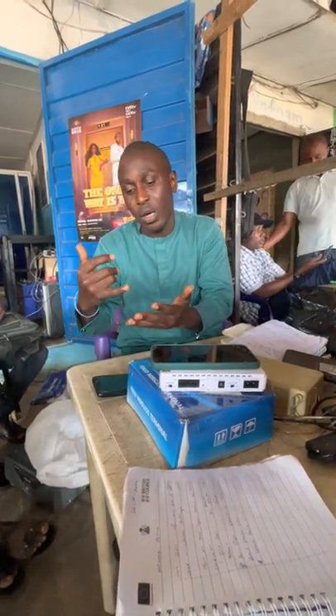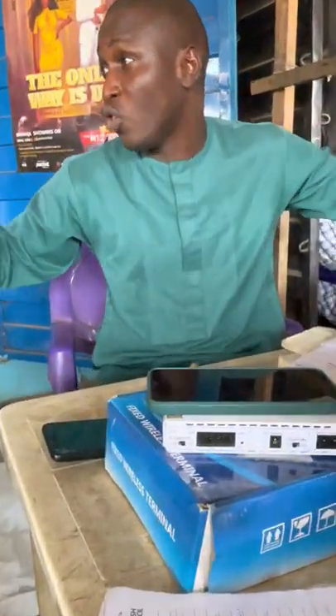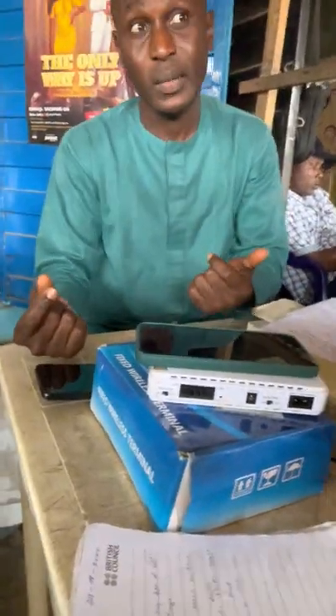Assuming we have 081 to 088, just 8 lines. Anywhere that I'm running is going for individual lines. But as an upcoming installer, it's better you use 2 pairs. Because if there is a problem with your main, you can easily move to pair 2, which is our redundancy. You guys get what I'm saying?